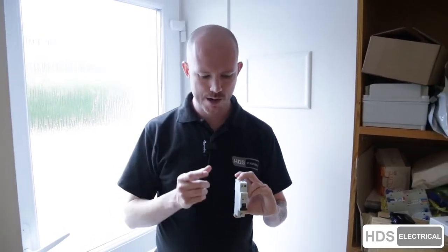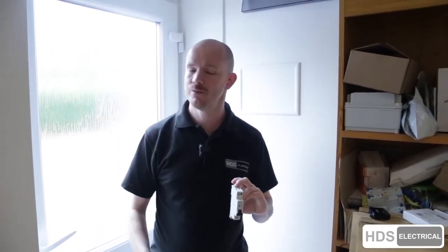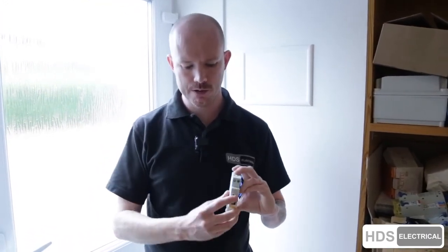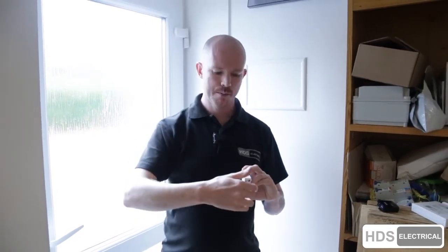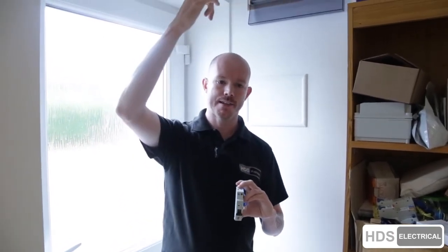The reason why that's good is because this will detect it escaping into the casing of the cooker or whatever and trip out, and it won't allow you to put it back on, because as soon as you try it will notice power coming down the live. The same amount isn't coming down the neutral because some's going into the casing of the cooker and trip out. That's how they work. That's how they save lives.